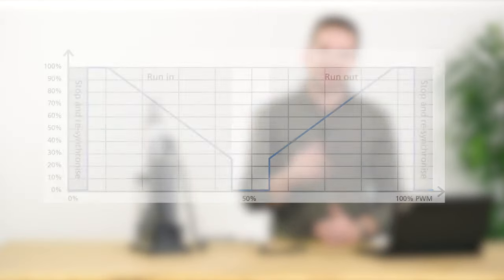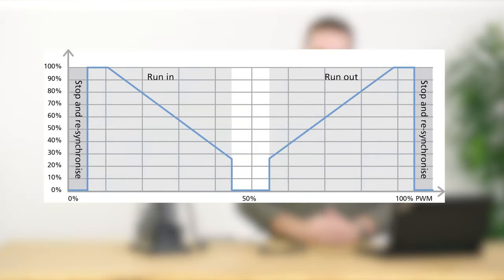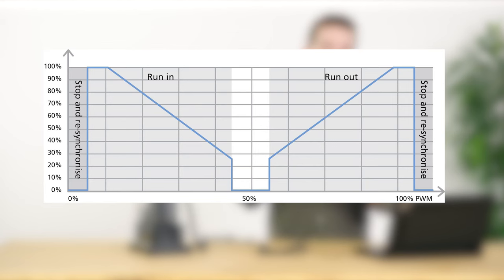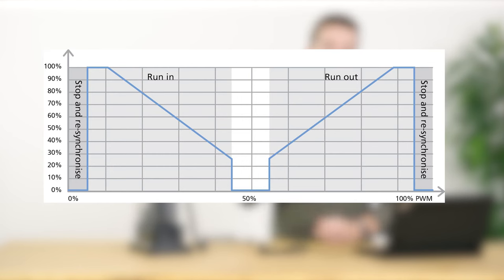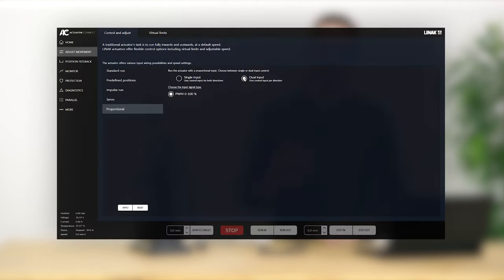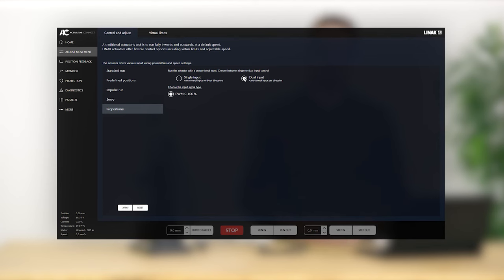For single control input, the actuator moves in both directions from one signal as shown here. The illustration gives a good idea of what that looks like. At 50 percent nothing happens, but over 50 percent you move outwards and under 50 percent you move inwards. There's a dead band on both sides, stopping in and stopping out. The actuator runs faster and slower depending on what input you provide. This input is applied to the red wire. In this case, the black wire is either not in use for PWM or uses a ground for the analog input current or voltage.